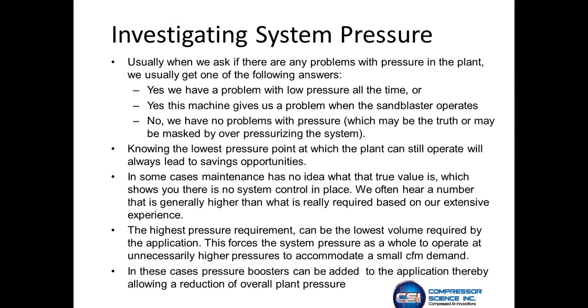And again, when we ask if there are problems, sometimes there's low pressure all the time, or this machine gives us a problem when the sandblaster operates, or our shot peen goes off, or we have no problems with overpressurizing. The most critical thing with pressure in the plant, obviously, is what is the lowest pressure that you can operate on and still have the plant function without any issue. And there's always a threshold there that we look at. If it's within 5 or 10 psi, we try to tell our customers to bring the plant pressure down 1 psi a week or 2 psi a week, depending on how high it is, and just let the system stabilize and make sure nobody complains. A lot of times we've had customers that have got down to 85 or 90 psi and had nobody complain.